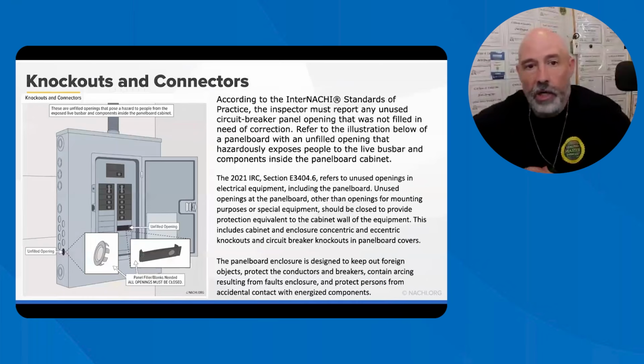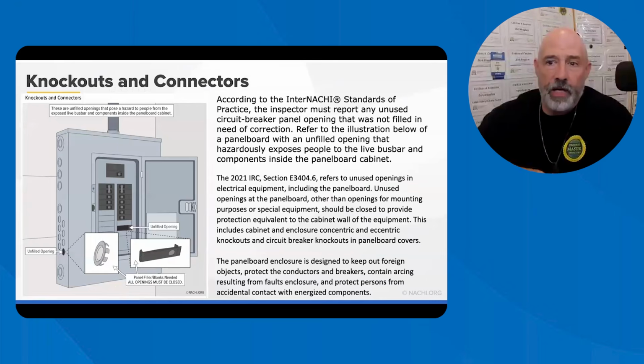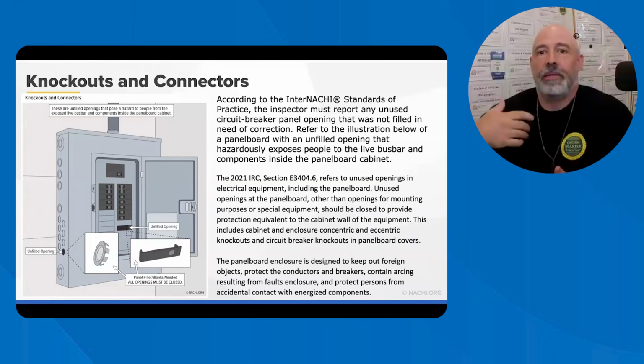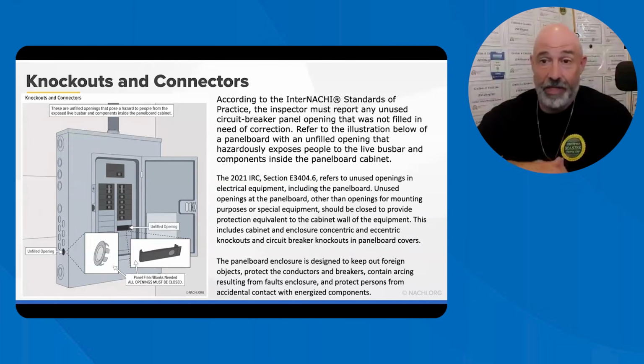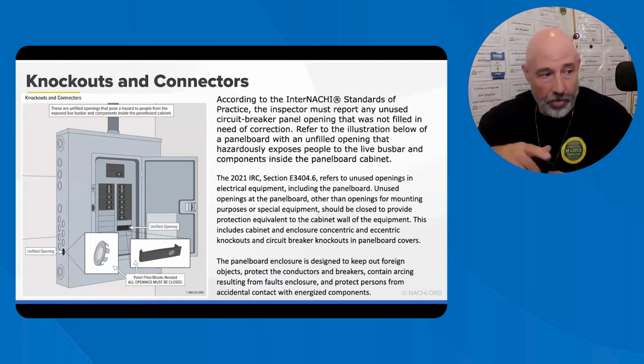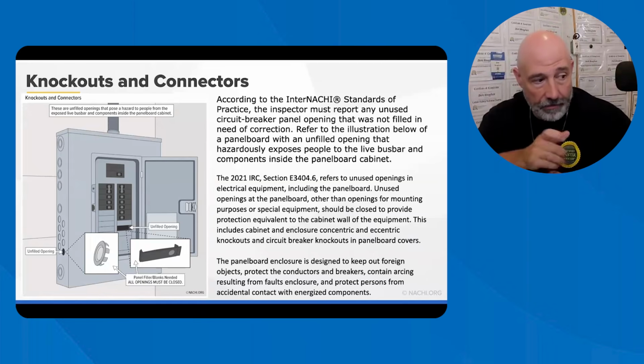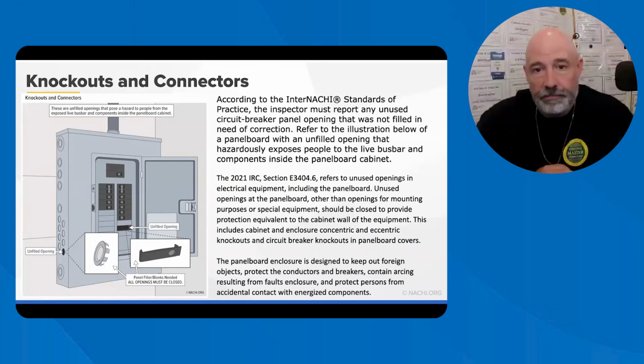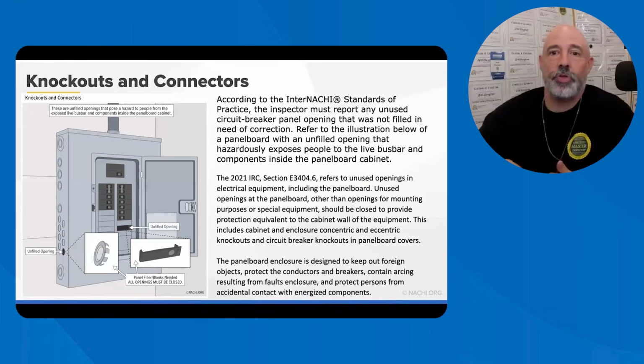So there you go. According to the InterNACHI standards of practice, the inspector must report any unused circuit breaker panel opening that is not filled in as in need of correction. So make sure that if you see that blank spot, you are referring to it as needing to be corrected. Refer to the illustration below, the little panel plug there, basically. I'm trying to blank on what that's called. Doesn't matter. The 2021 IRC section E3404.6 refers to unused openings in electrical components, including the panel board, unused openings in the panel board other than openings for mounting purposes or special equipment.